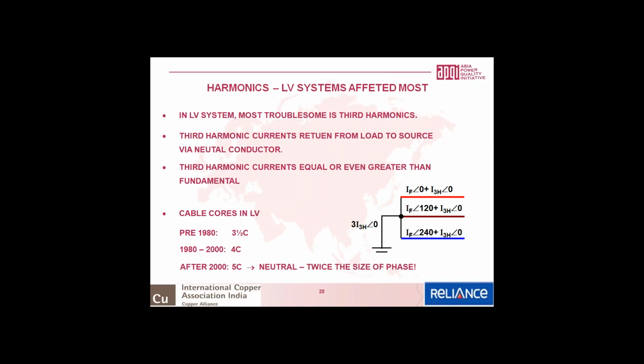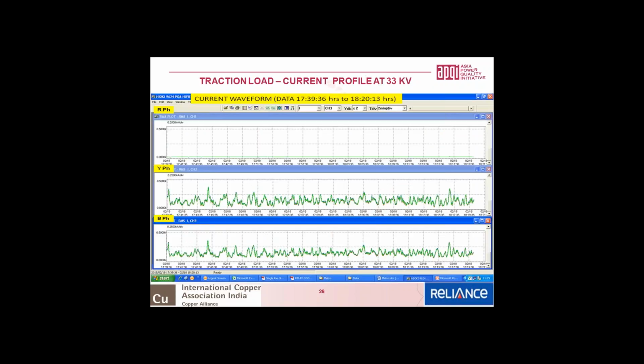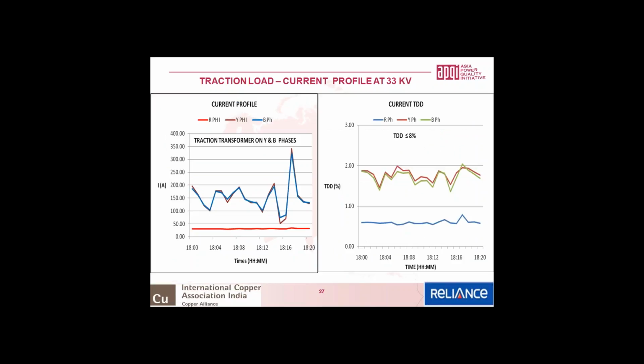Of course, to prove the point that at high voltage levels harmonics do not have too much effect, this is a current waveform taken for a traction load. You can see on the top that since traction loads are connected only between two phases, Y and B, you see current on the Y and B phases only. The extracted current is shown on the left, and we are not showing THD, because THD is applicable only for voltage.